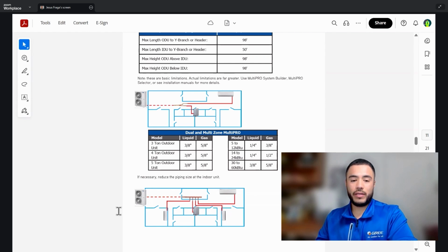And so below is an example of a multi-zone with a header installation. It's important to really centrally locate this. That way you don't have any really far line set connections that are coming off of this header. So as we see here, they're all pretty much close to the same sizes, except for this one right here in the middle. But pretty much the basic concept is centrally locate that header. That way you have reduced piping to do whenever you're out in the field.